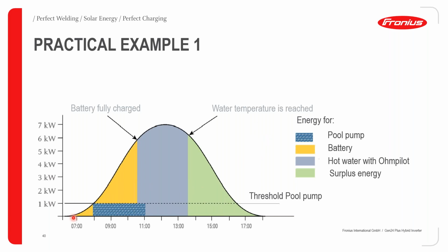We have a scenario with PV production starting at 7 a.m., which kicks in by charging the battery, as shown in the region shaded yellow. When the feeding power gets to 1 kilowatt, that's the threshold signal point or turn-on point for the pool pump.